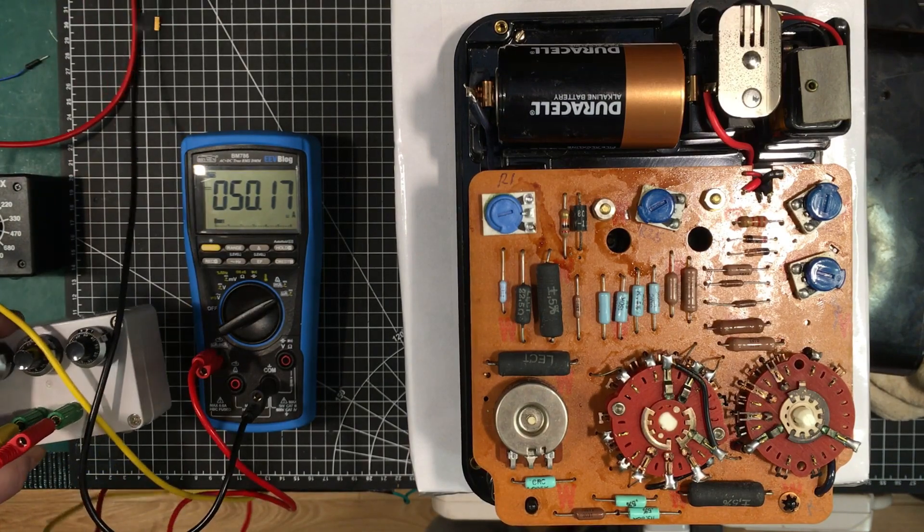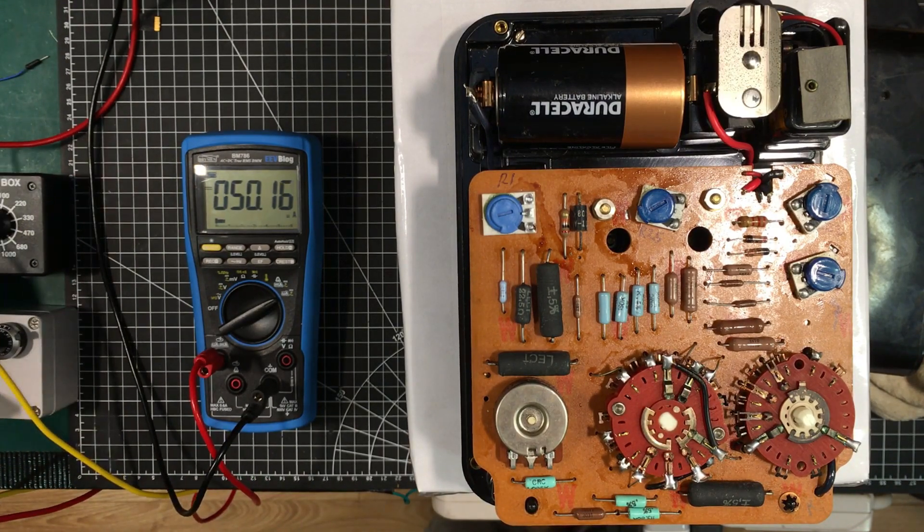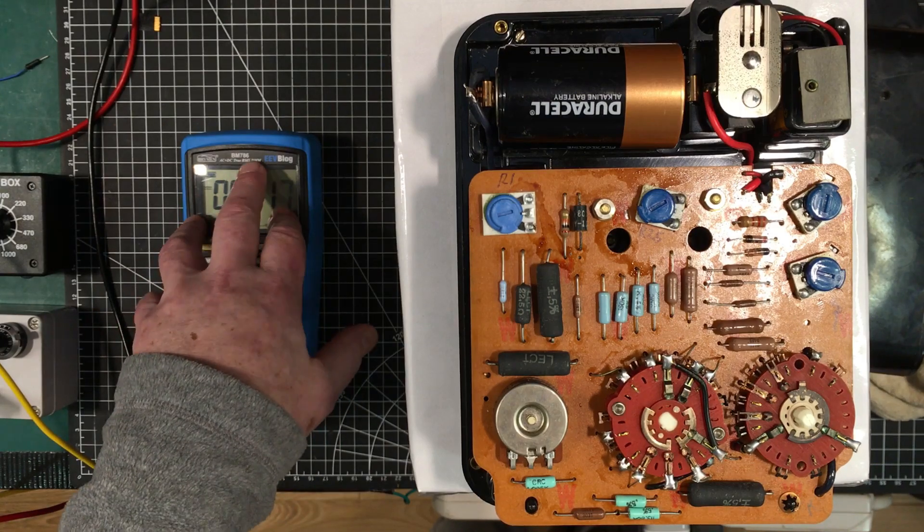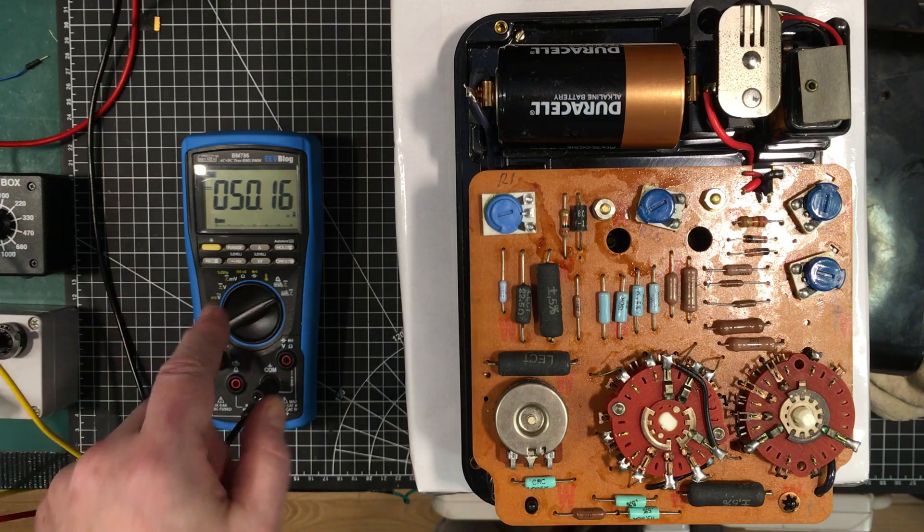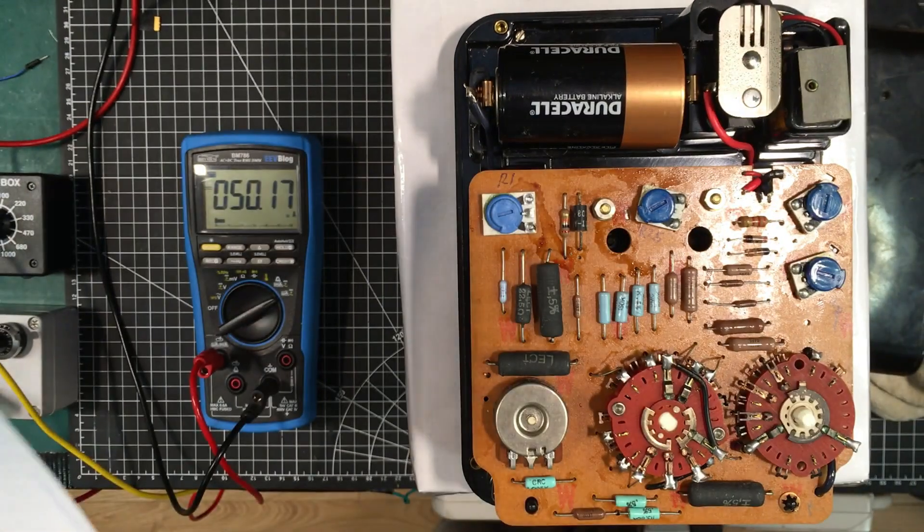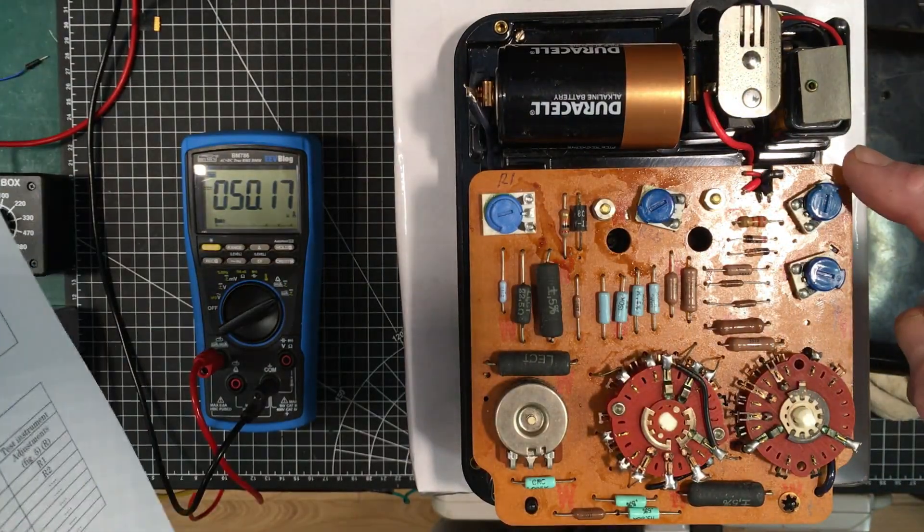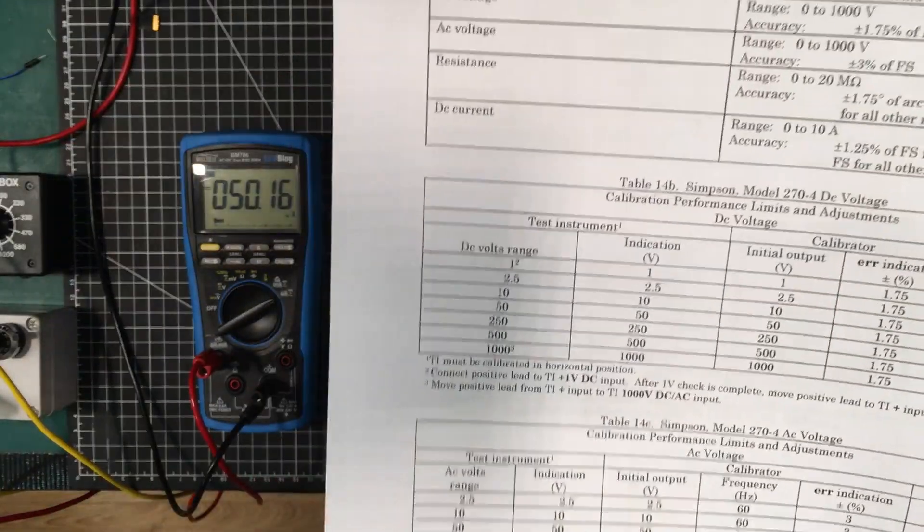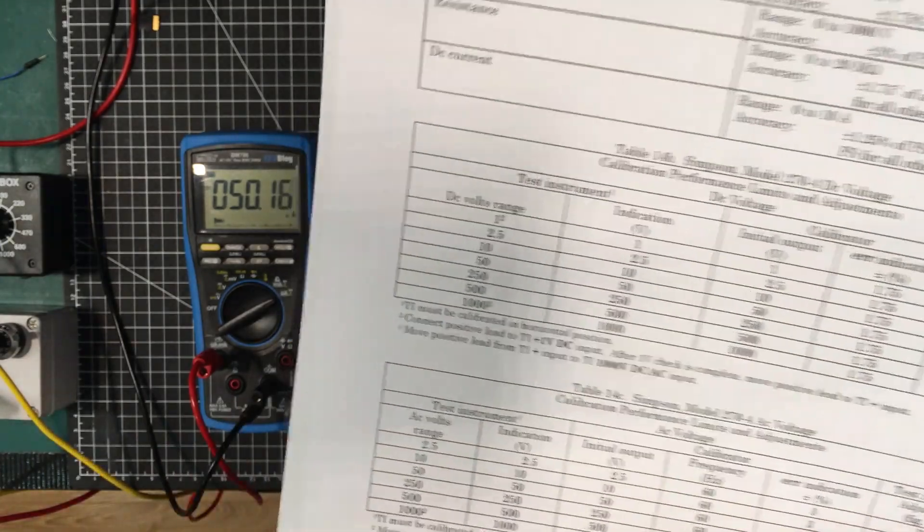I've got these little resistance boxes here to help me set the current properly. Right now I've got 50 microamps running through the BM 786. Once you connect it up we'll have to adjust that a little bit to get 50 microamps exactly, and then this should be reading full scale. If not we'll adjust R1, then bring it up to 1 milliamp and if necessary adjust R2.